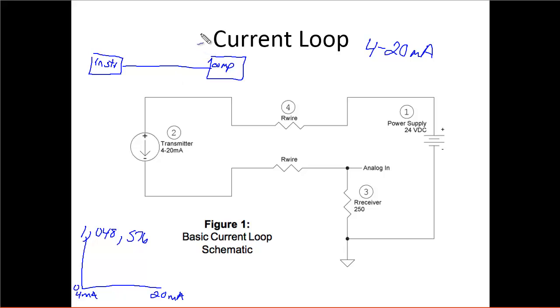So in all these cases, the current loop actually comes out to be a nice way to do this. So the reason they do 4 milliamps to 20 milliamps is that as long as you're getting 4 milliamps, you know that this instrument is working out there even though it's reading zero. If we did say zero to 16 milliamps or zero to 20 milliamps, then this instrument could drop off or something could be wrong with that instrument. I'd get zero, I'd show zero milliamps or somebody could break the line. I'd get zero milliamps here and I would have no idea that I wasn't connected to my instrument. I would just think I was reading zero. So doing 4 milliamps, I at least know that I've got some current going through here and I know that it's working.